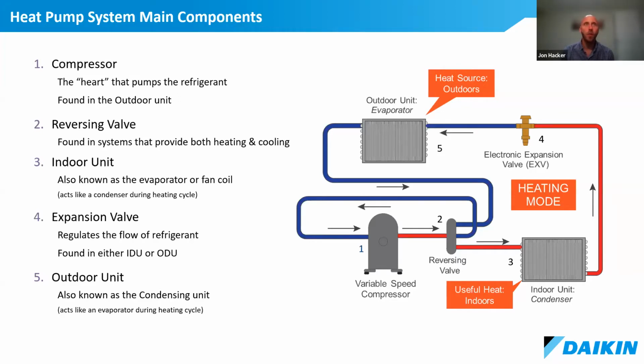I'm showing a basic diagram here of the main components of a heat pump system. The inverter itself, as we've discussed, is applied on the compressor, and that's because the compressor is the main energy consuming device, and it's really doing all of the work to complete a refrigeration cycle. Item number 2 is the reversing valve, and that's really the only main difference between an air conditioner and a heat pump. It simply reroutes the refrigerant depending on if the system is in heating mode or cooling mode, and by changing the routing, you're able to reject heat into the space or reject heat outside, thus providing heating or cooling.